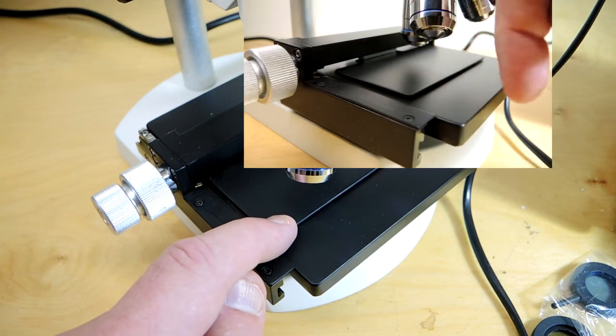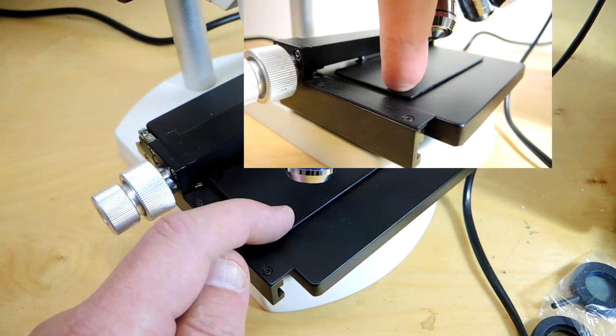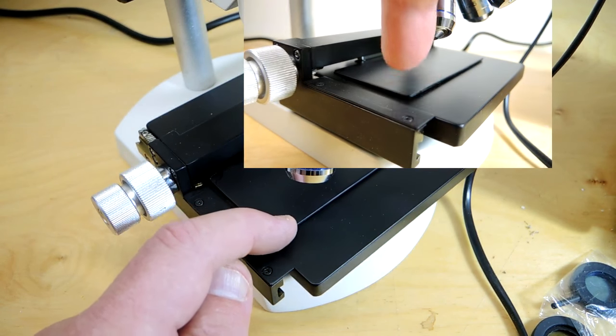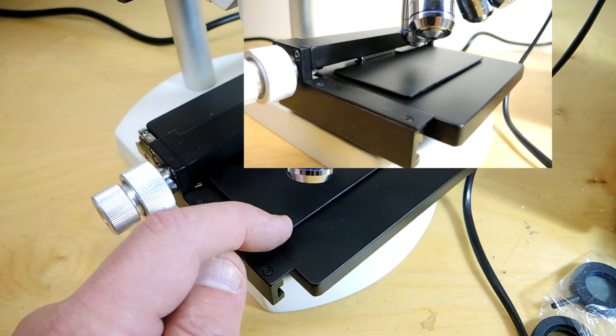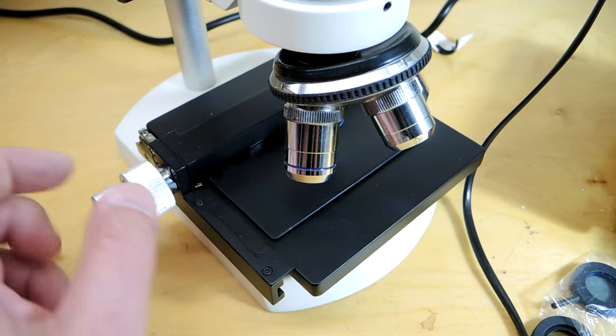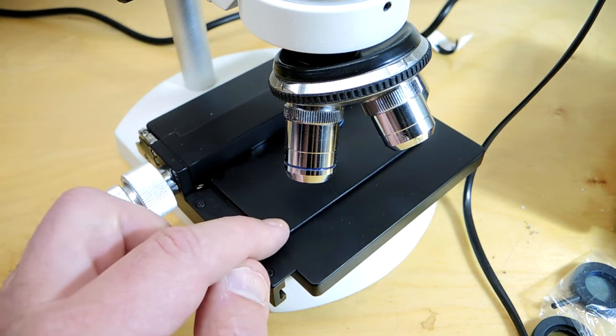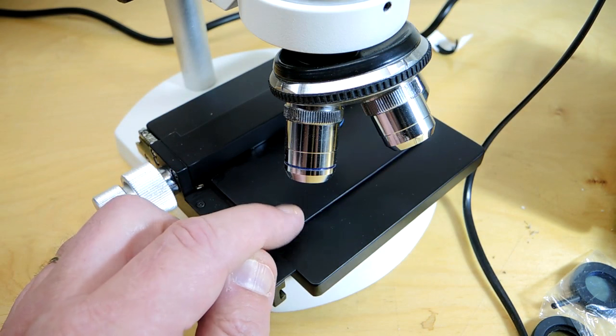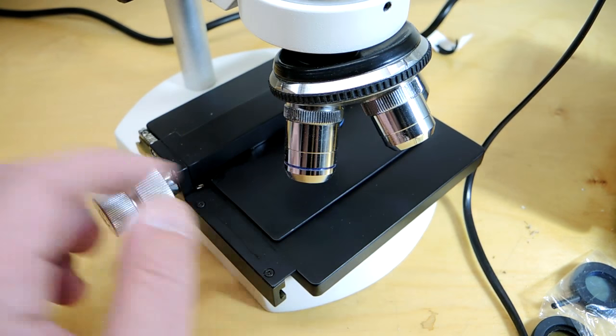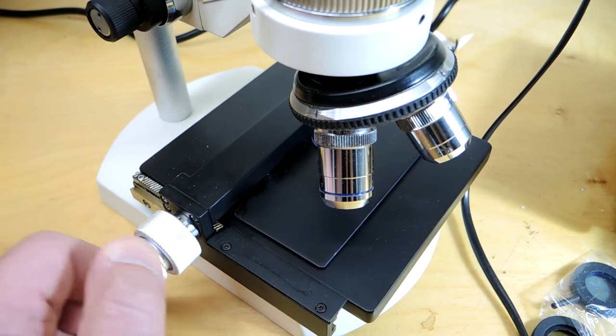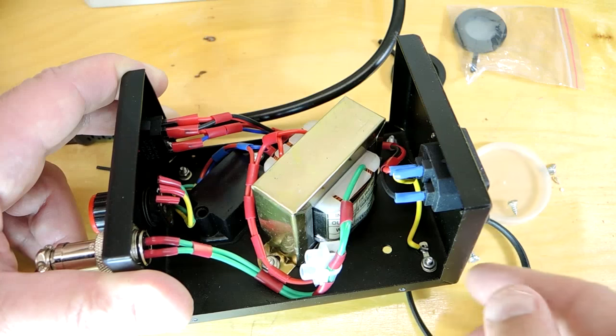The stage itself, I'm just putting a side view on it. You can see, unfortunately, it flexes a little bit in this microscope. Now, fortunately, I'm actually looking at really, really light sample semiconductors, but if you're doing a true traditional metallographic type thing where your samples might be kind of heavy, this might be a little bit weak for that, but for my purposes, it works very well.